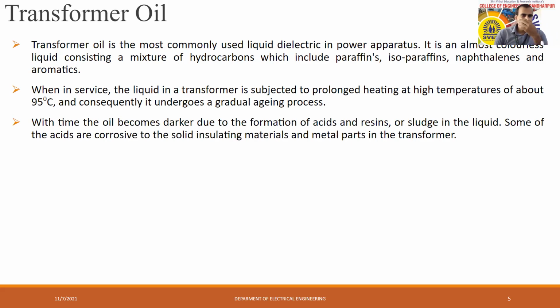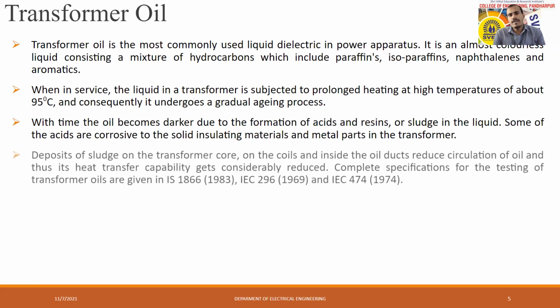So with time, whatever the oil becomes, as time passes, this oil will become an acid or resins, and some of that acid will become corrosive, which may impact the metal parts of the transformer or the solid parts of any apparatus. So these oils or liquids can sludge our transformer core, and whatever ducts are there, it can reduce the flow of oil, and thus reduce the heat transfer capability we are talking about.